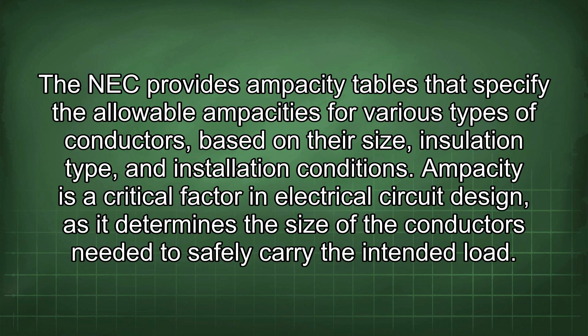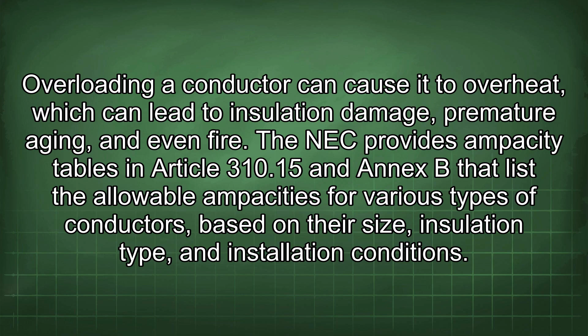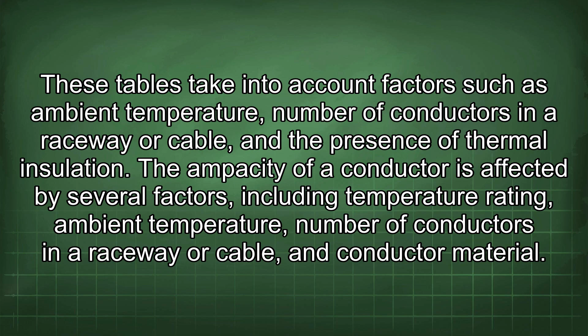carry the intended load. Overloading a conductor can cause it to overheat, which can lead to insulation damage, premature aging, and even fire. The NEC provides ampacity tables in Article 310.15 and Annex B that list the allowable ampacities for various types of conductors based on their size, insulation type, and installation conditions. These tables take into account factors such as ambient temperature, number of conductors in a raceway or cable, and the presence of thermal insulation. The ampacity of a conductor is affected by several factors, including temperature rating, ambient temperature, number of conductors in a raceway or cable, and conductor material.